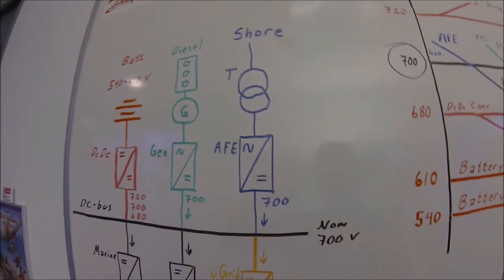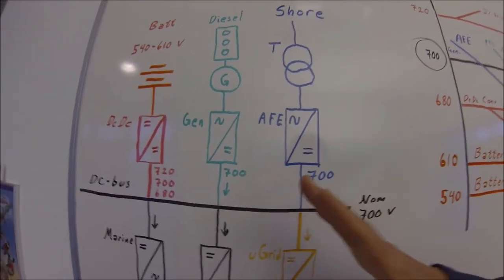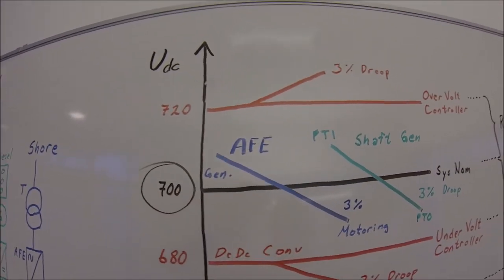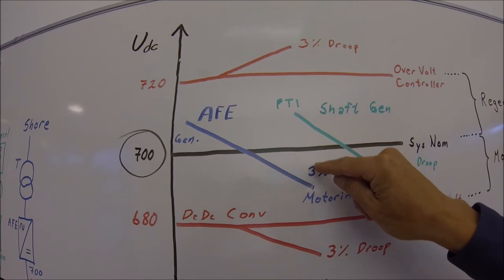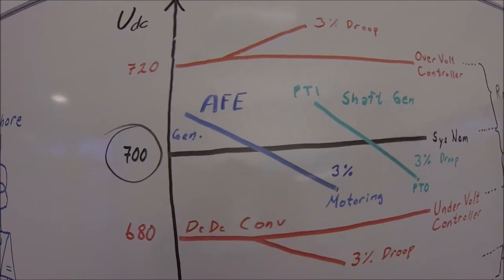The traditional active front end usually works around a nominal voltage and have a load drooping on the voltage. It's seen like here. Selected 700 volt, it will droop off 3% of its voltage as a function of the nominal current.